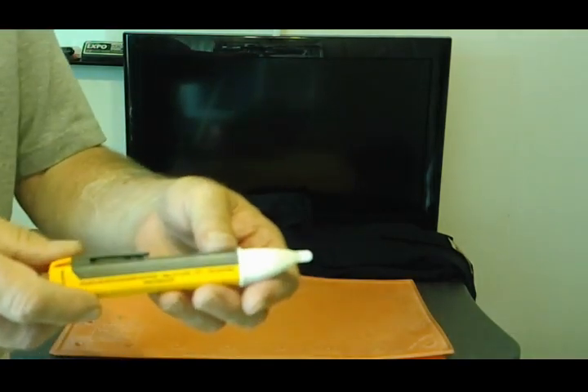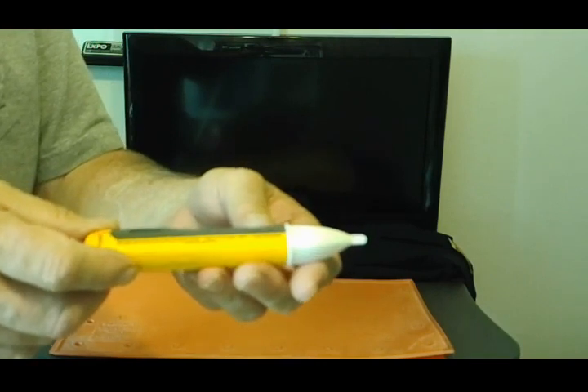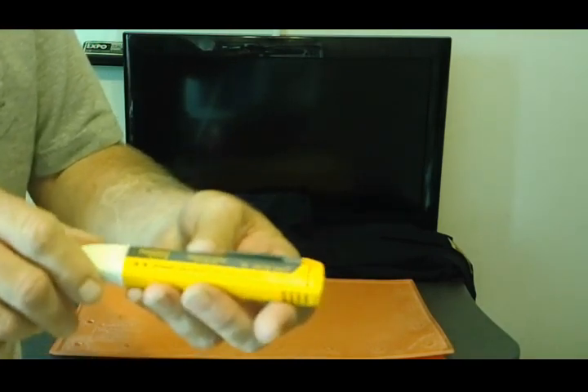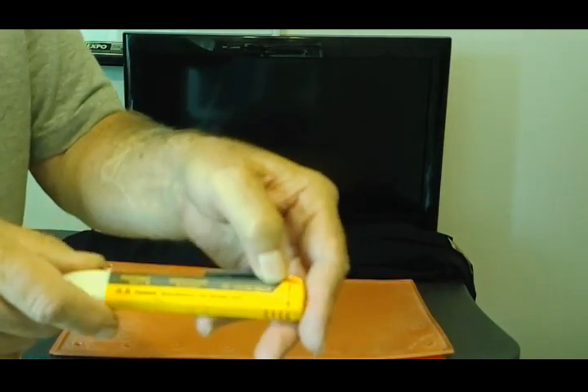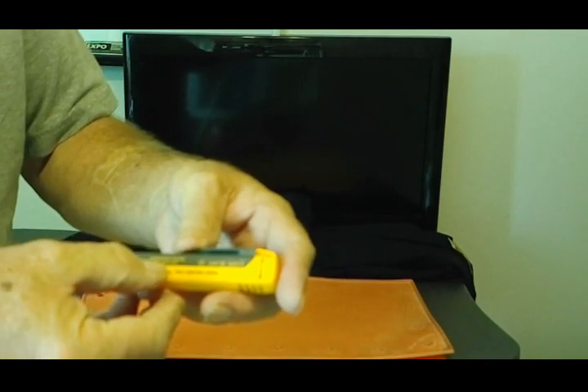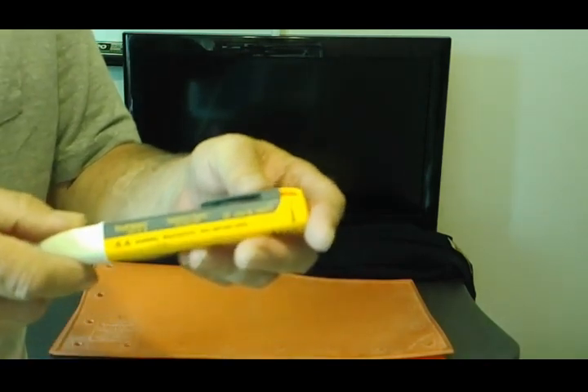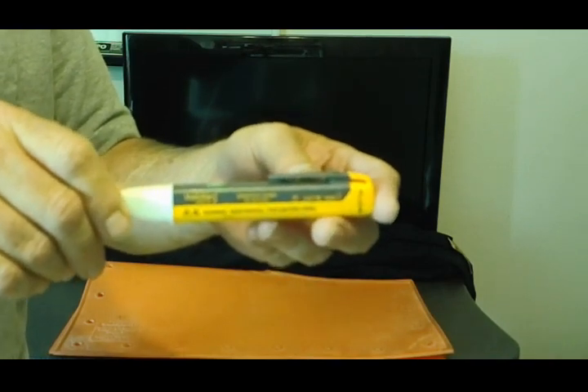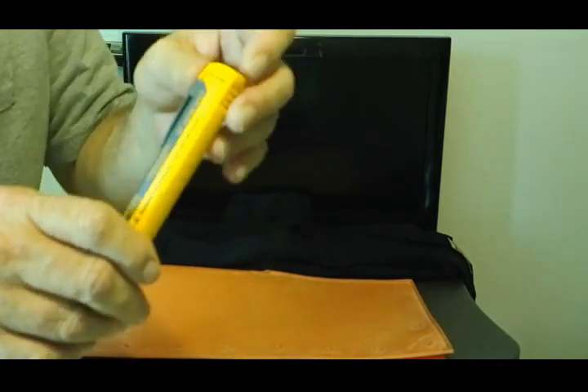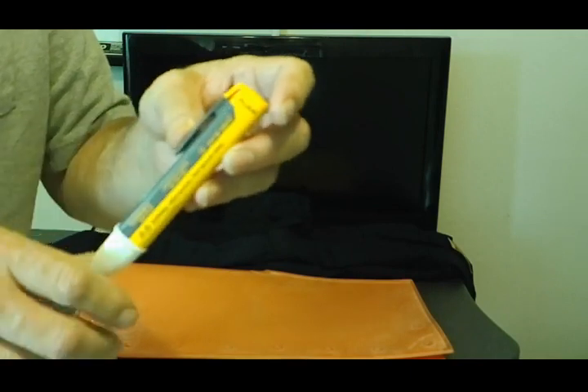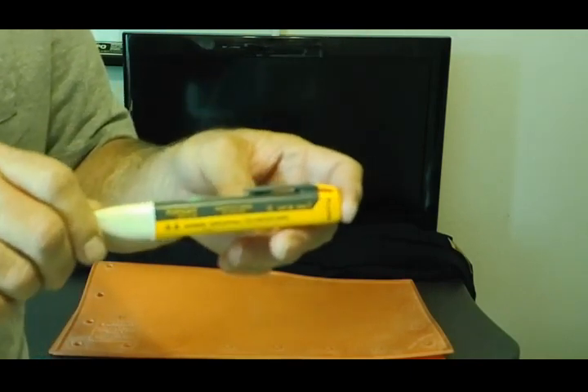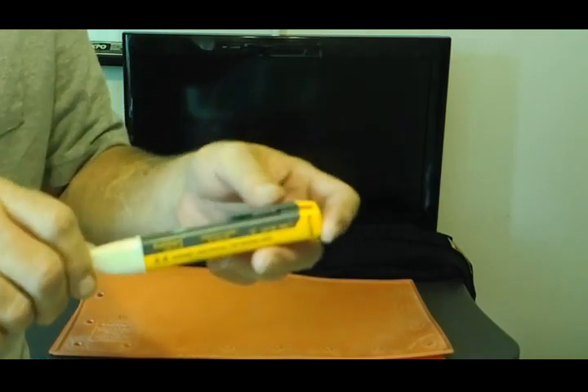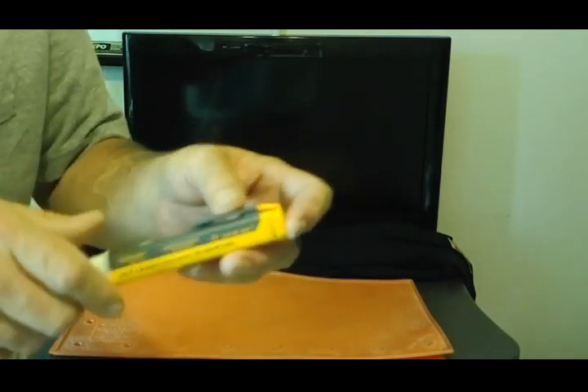Now, one of the things commonly used in industry is a tick tracer. These are good tools to use if you understand them and use them correctly. First of all, this tracer right there is rated Cat 4 to 1000 volts. It could be used from 90 to 1000 volts AC. This is safety equipment. All the meters are safety equipment. Problem is, with this one, you drop it, it breaks. If the battery inside of it goes weak, it doesn't read within its ratings. So in other words, you can't trust them. You've got to test them before you use them. That's how they got the name Widowmakers. People didn't test them.